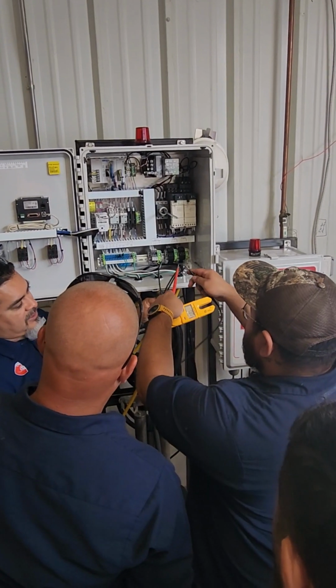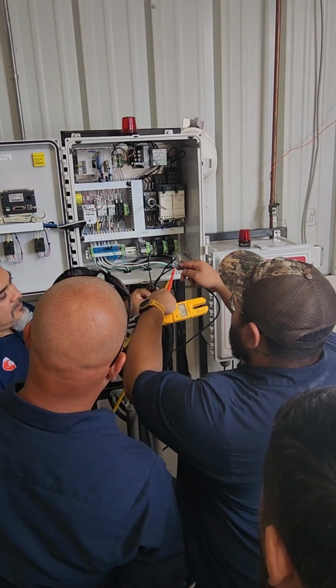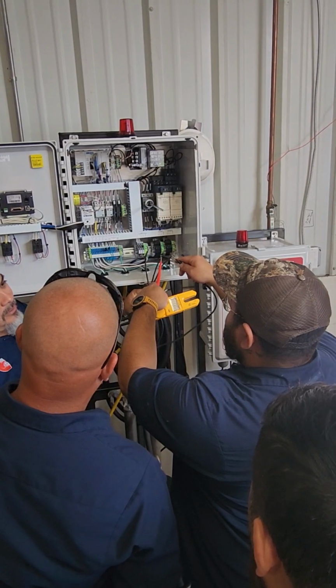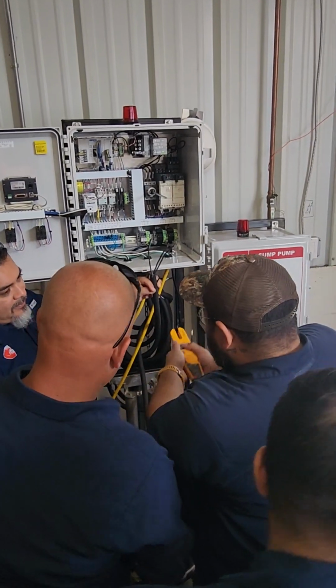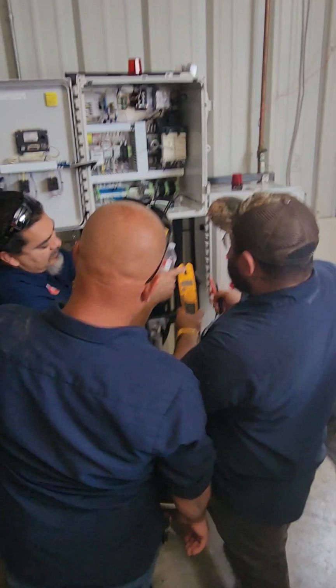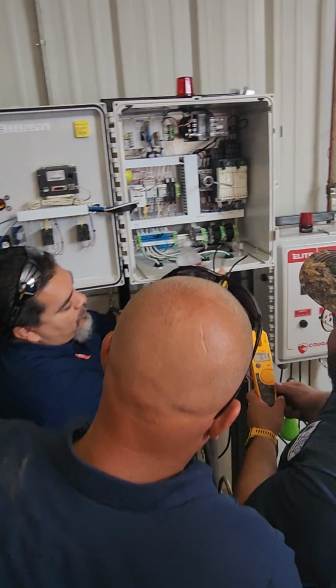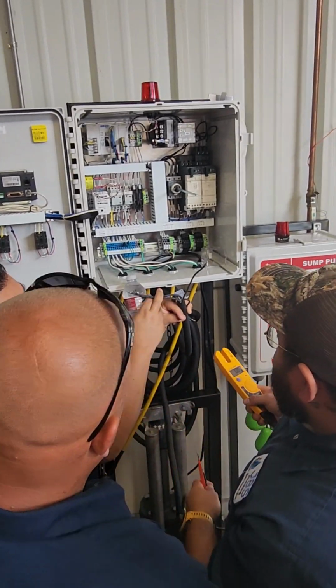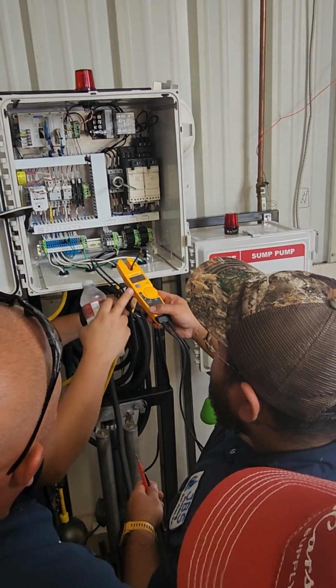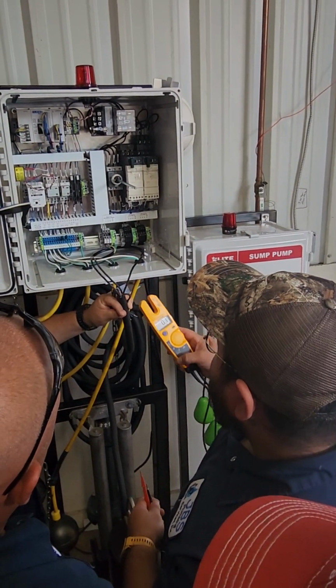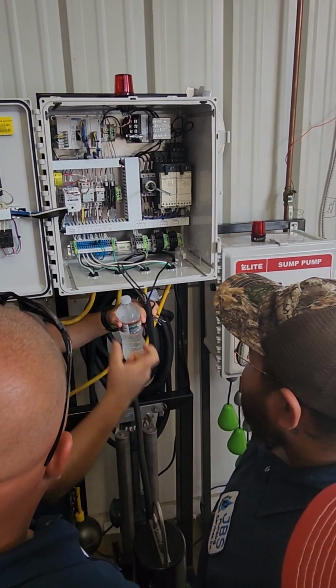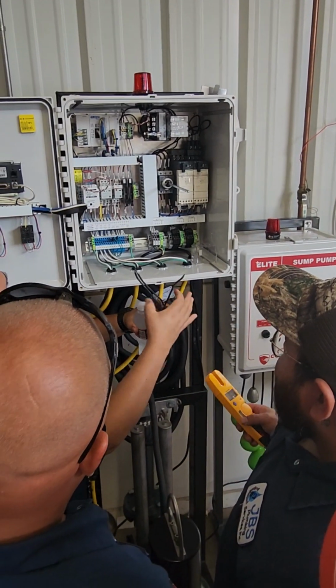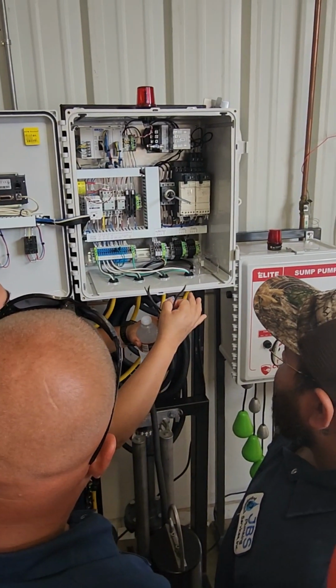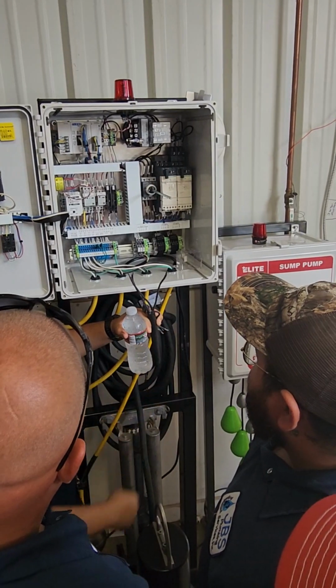For example, how will you check your amp? See, that's where you check your continuity and all of that. No, I already switched it over. Okay, so this is your clamp. So you will run one cable through that, and if it's running, it will indicate the amps. Some people have the clamp. So just one wire, not 3 wires, just one wire to show you how many amps is on that.